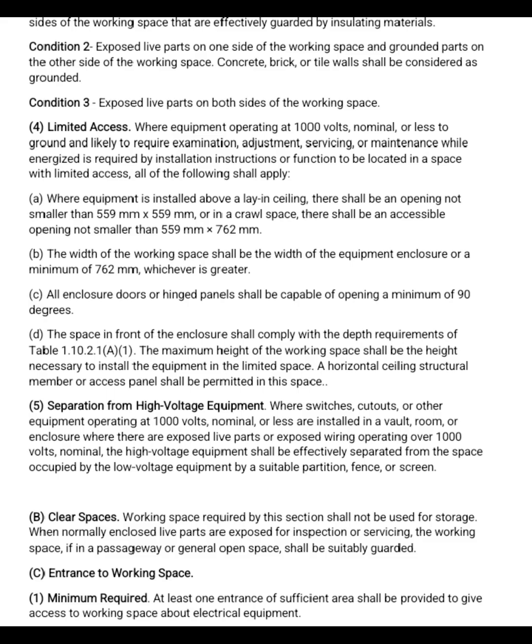B. Clear space. Working space required by this section shall not be used for storage. When normally enclosed live parts are exposed for inspection or servicing, the working space, if in a passageway or general open space, shall be suitably guarded.